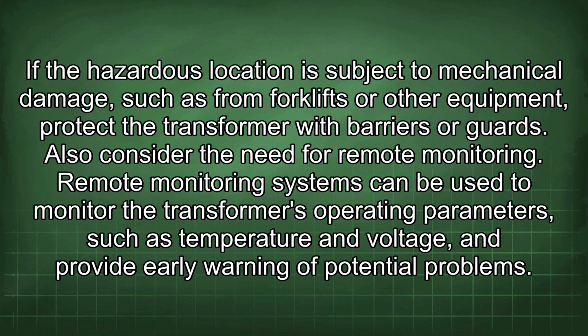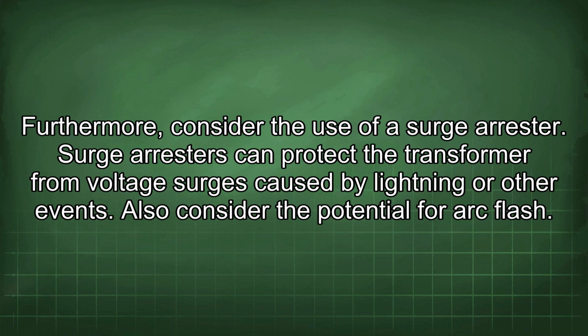If the hazardous location is subject to mechanical damage, such as from forklifts or other equipment, protect the transformer with barriers or guards. Also consider the need for remote monitoring. Remote monitoring systems can be used to monitor the transformer's operating parameters, such as temperature and voltage, and provide early warning of potential problems. Furthermore, consider the use of a surge arrestor. Surge arrestors can protect the transformer from voltage surges caused by lightning or other events.